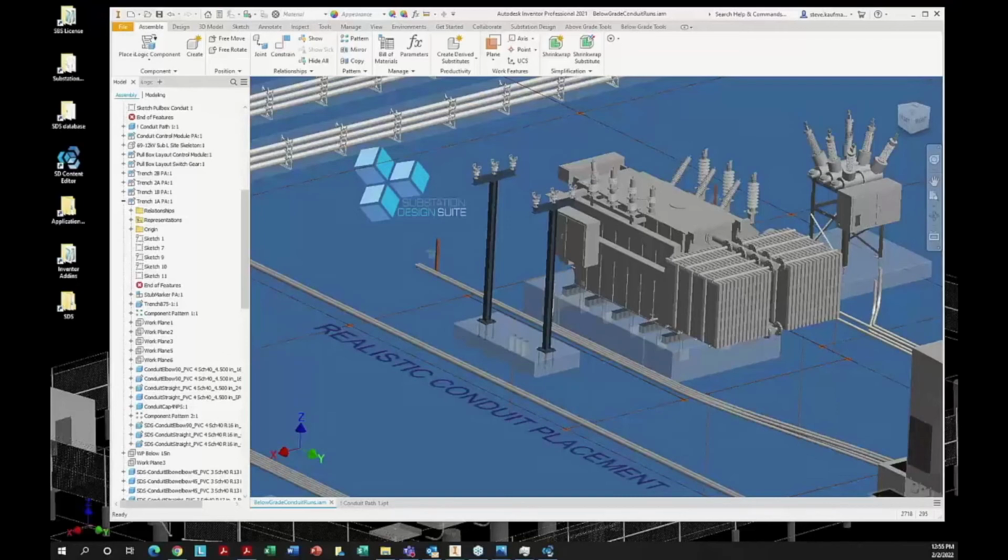There are some new tools in there, which came out about a year and a half ago or more, and they're able to do that. It actually paths things through the substation, kind of like your phone gives you a path to 7-Eleven. If you want to go to 7-Eleven for a super gulp, you can put in, I want a super gulp at 7-Eleven. Your phone's going to tell you how far away, where you turn, and such as that. We're able to do something similar by putting WorkPoints in our station and running those paths. If we know where that path is, we know where it's running in the trench or the conduit, and we know how many cables could be in that conduit.